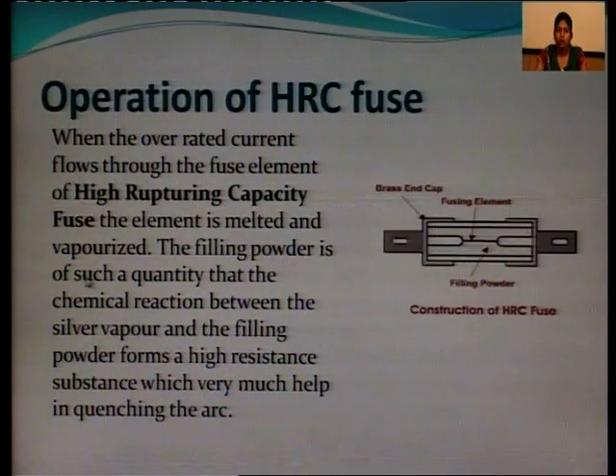The filling powder is of such a quantity that the chemical reaction between the silver vapor and the filling powder forms a high resistance substance, which greatly helps in quenching the arc. When melting occurs, an arc is produced between the two contacts, and the powder starts to vaporize. Due to the chemical reaction of this gas, we are able to extinguish the arc.